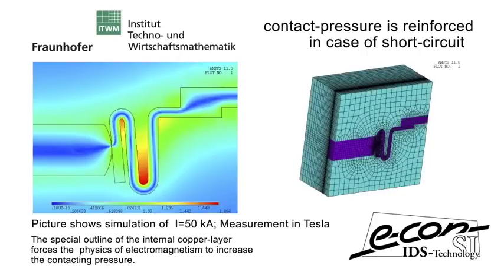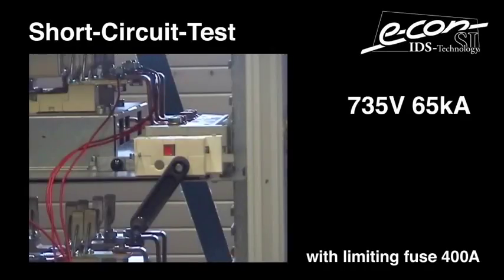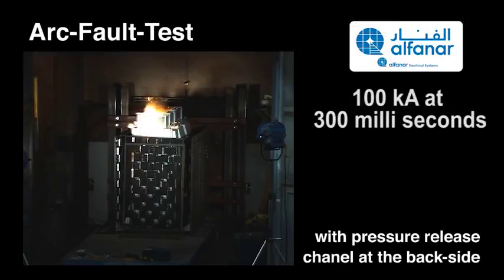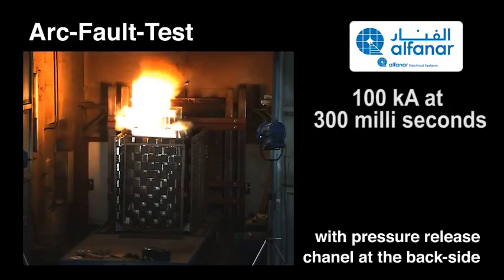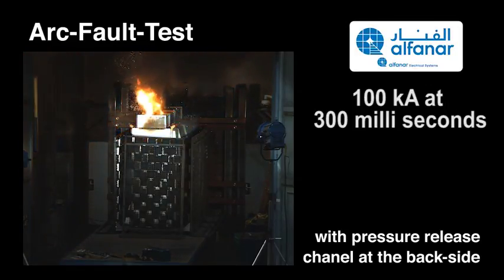The contact will always be pressed further to the bus bar no matter how severe the short circuit will be. The video shows the contacting device tested at the voltage level of 735 volts, 65 kiloamperes with 400 ampere fuses. The special construction of the complete system allows the installation of an internal arc fault exhaust duct at the top side of the switchboard panel. An arc fault test of 100 kiloamperes for 300 milliseconds has been successfully passed.